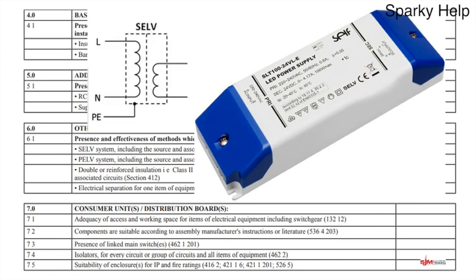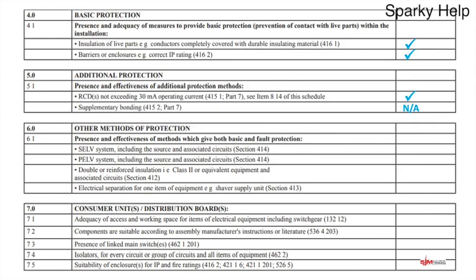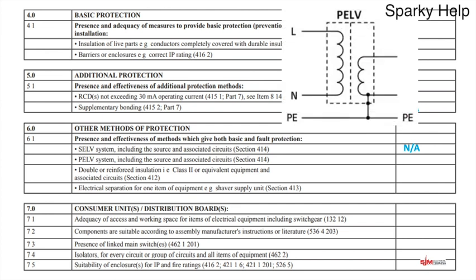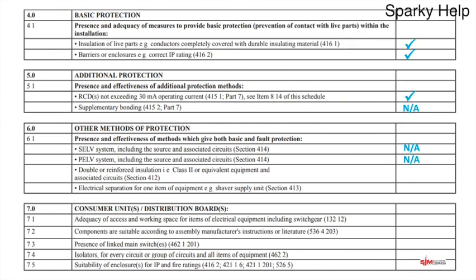The only way you can get a shock off of it, and it wouldn't be much anyway, but don't go trying it, is touch both conductors. So if you've got any of these fitted within an installation and you've got circuitry associated with it, it will become a tick. If you haven't got any, it becomes an NA. The next one is PELV. That's a similar type, but again you'd have to check to see what you've got installed. But PELV is a similar type of transformer. It's extra low voltage, but it's protective extra low voltage, but this time it is tied down to earth and therefore potentially could get shocked. So things will be earthed as they go on the output side, but you'd need to check to see what type of transformer you have and have a look, see if we've got it, but the chances are it's probably going to be an NA.